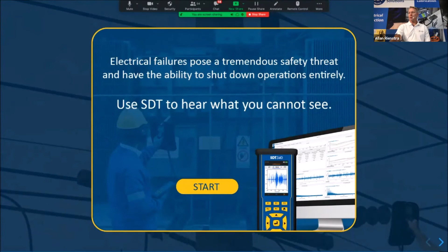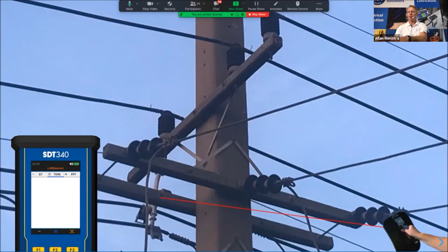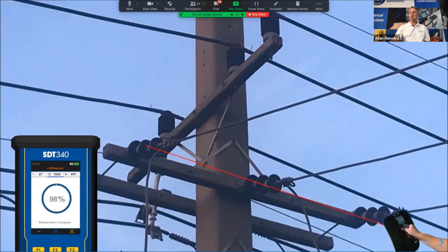We can find corona on a lightning arrestor with the SonaView, using ultrasound. We can have a little demonstration here: this is my parabolic dish, I've got my laser, and I can point it. This is my ultrasound detector over here. When I find some corona, I take a measurement and I can see a time waveform. The audio is very low on this, I apologize. Here we have another pole, and we just scan, scan, scan. It's here somewhere... where is it... oh, there it is.